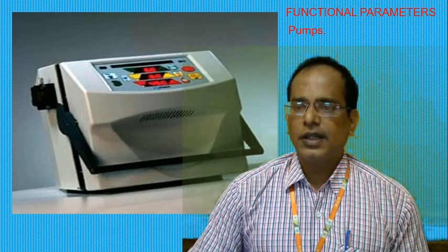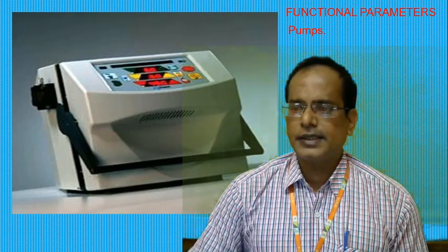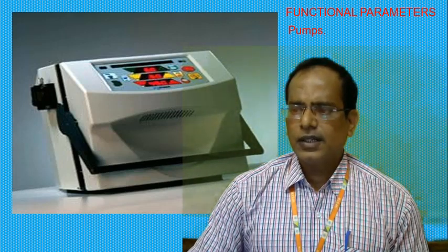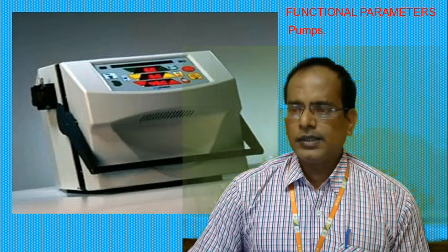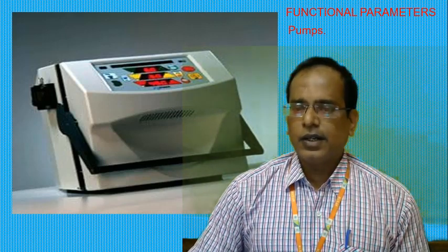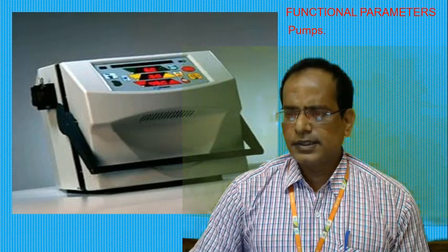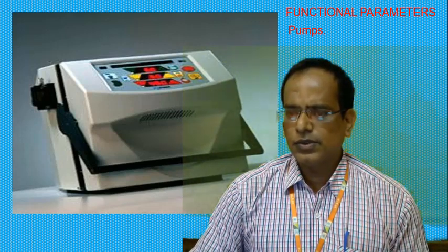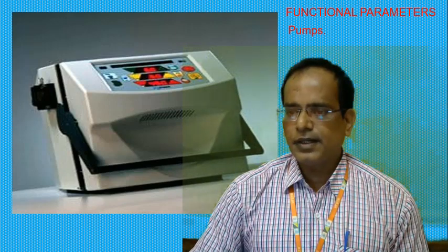These pumps require a significant amount of power and are driven by either DC or AC motors with variable speed control. Electronic means must be provided to ensure the motor turns at the desired rate. A Hall-effect sensor gives a fully independent signal from the actual shaft rotation, which can be used for redundancy. For lower volumes of fluid, a syringe pump mechanism is commonly used, driven by a smaller stepper motor or DC motor, providing precision measurement.